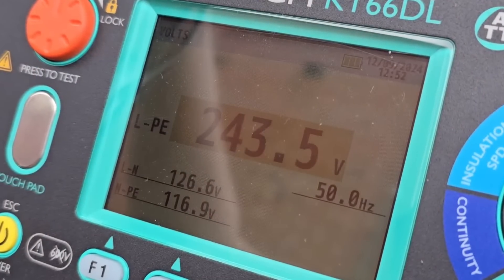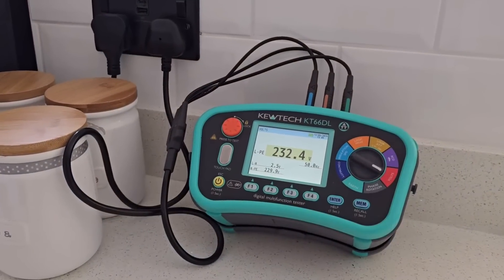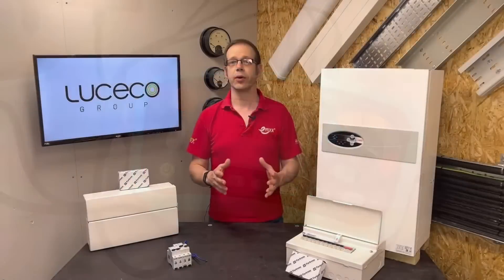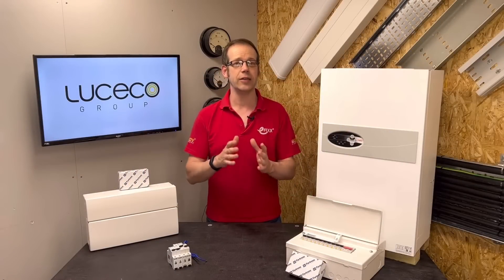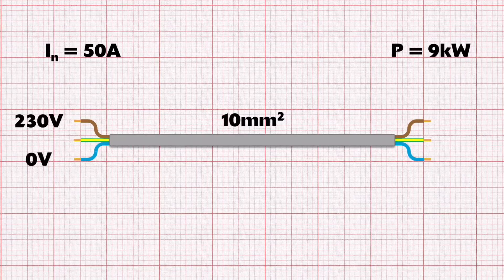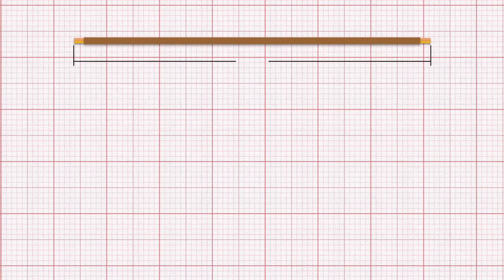Whatever voltage we measure across the incoming terminals of our consumer unit, we will always get less at different points in our installation because of the volt drop. If current is flowing through a conductor, there must be a difference in voltage between any two points in that conductor. We tend to think of the line conductor being at 230 volts and the neutral at zero volts, and therefore when we connect a load between them, current will flow through the load due to the difference in electrical pressure between those two conductors. But if we take a short section of line conductor just one metre long, and current is flowing through it, there must be a difference in voltage between those two points a metre apart.